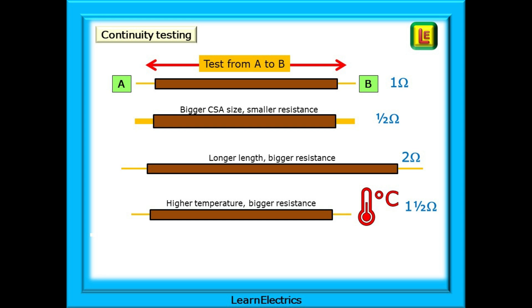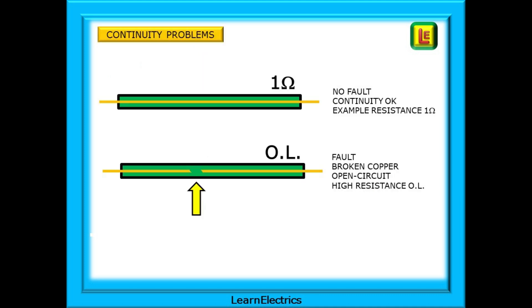However, if we make the cable twice as long the resistance will double in value as there is now a longer length and it is harder for the current to flow through it. Then there is the temperature to consider. Copper will change resistance slightly as the temperature changes. A conductor measured at room temperature will increase in resistance value as the temperature rises. With copper conductors we have a limiting temperature of 70 degrees Celsius and we always try to keep the temperature below this.